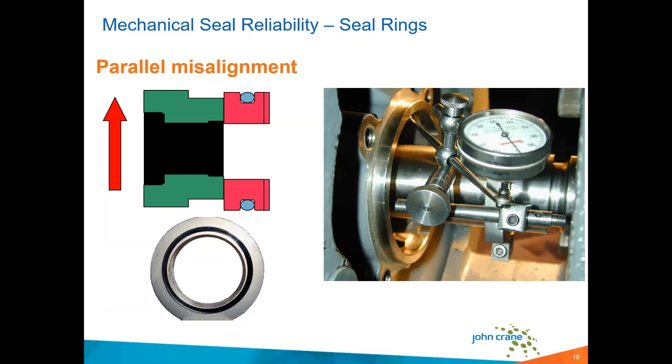So really, the resolution is you need to address the concentricity issues if they are present, and doweling bearing housings, having a good fit on your repeatability and your support of your bearings and of your shaft, all of those are good practices to look at. But it all starts with doing the checks and doing the due diligence to make sure you're eliminating those issues if they are there.